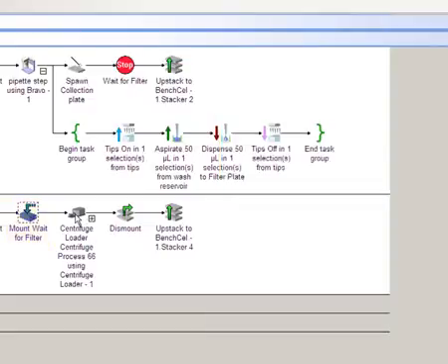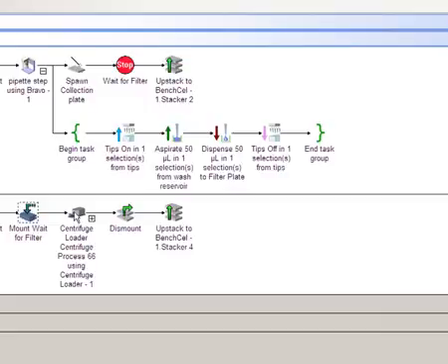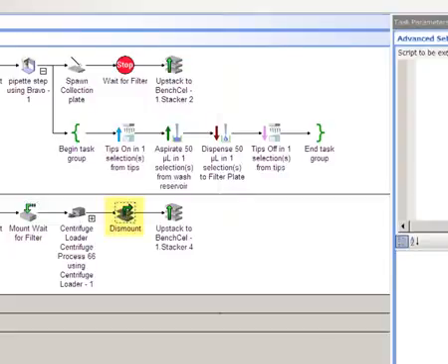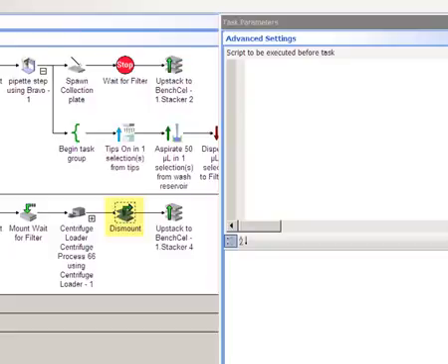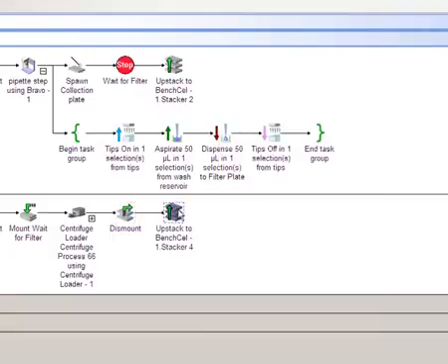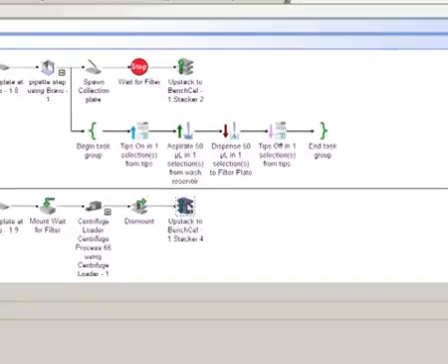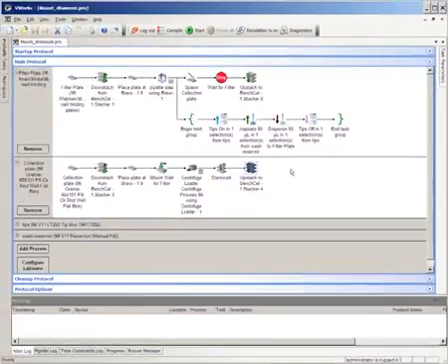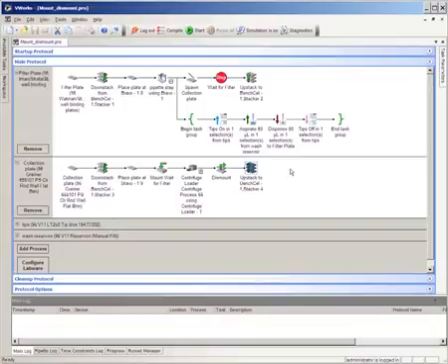The eluent is collected during the centrifuge process. When finished, the dismount task removes the filter plate from the collection plate. Notice that the dismount task does not have any task parameters. After the dismount, the collection plate returns to the specified BenchCel stacker. And that's how you use the mount and dismount tasks.